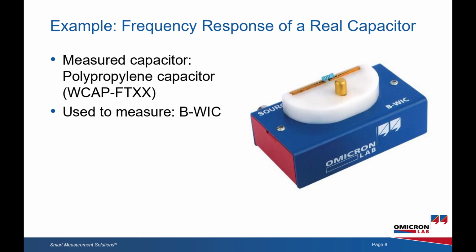Now let's measure a capacitor. I'll measure a polypropylene capacitor, the WCAP FTXX. For this measurement, I'll use a BWIC test fixture, since the expected impedance range fits well within the BWIC measurement range, and the fixture is designed for this type of measurement.